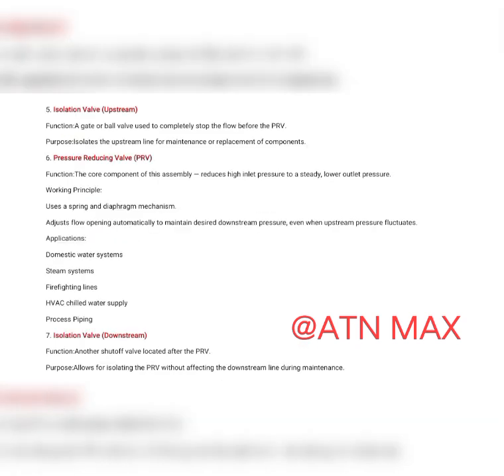5. Isolation valve, upstream. Function: a gate or ball valve used to completely stop the flow before the PRV. Purpose: isolates the upstream line for maintenance or replacement of components. 6. Pressure reducing valve, PRV. Function: the core component of this assembly, reduces high inlet pressure to a steady, lower outlet pressure.